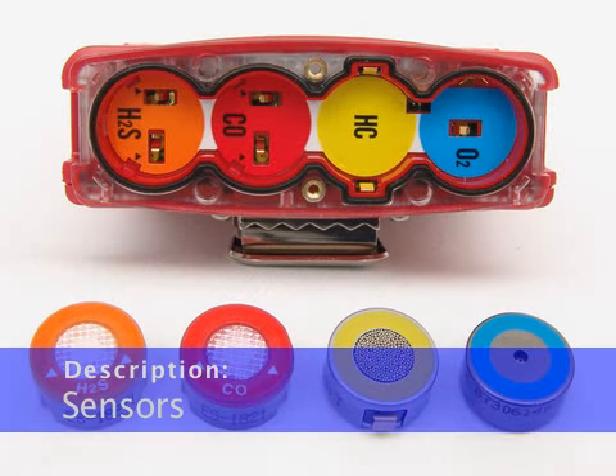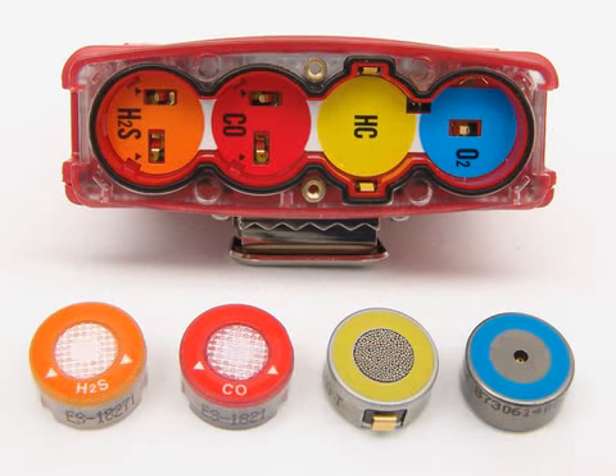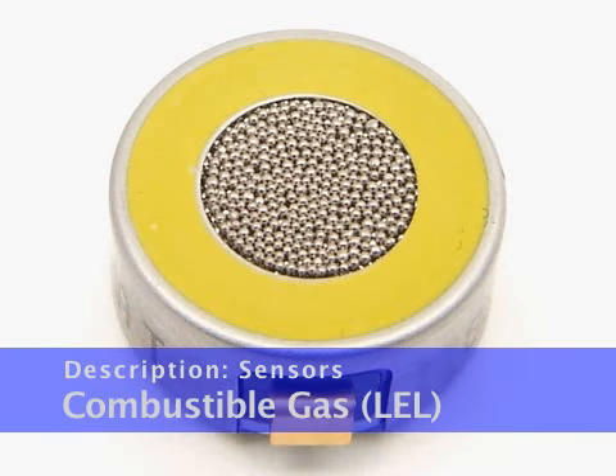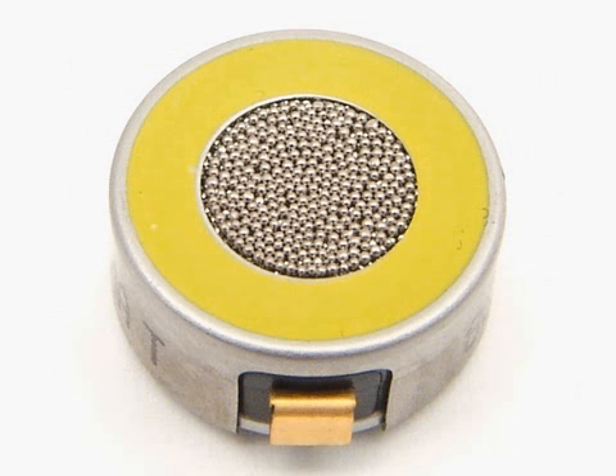The GX-2009 uses 4 sensors to monitor combustibles, oxygen, carbon monoxide, and hydrogen sulfide simultaneously. The combustible gas sensor detects combustible gas and vapors in the lower explosive limit range, or LEL, with a catalytic element. A sintered metal flame arrestor covers the element and allows ambient air to diffuse into the sensor. The reaction of gas with oxygen on the catalyst causes a change in the resistance of the element, which affects the current flowing through it.